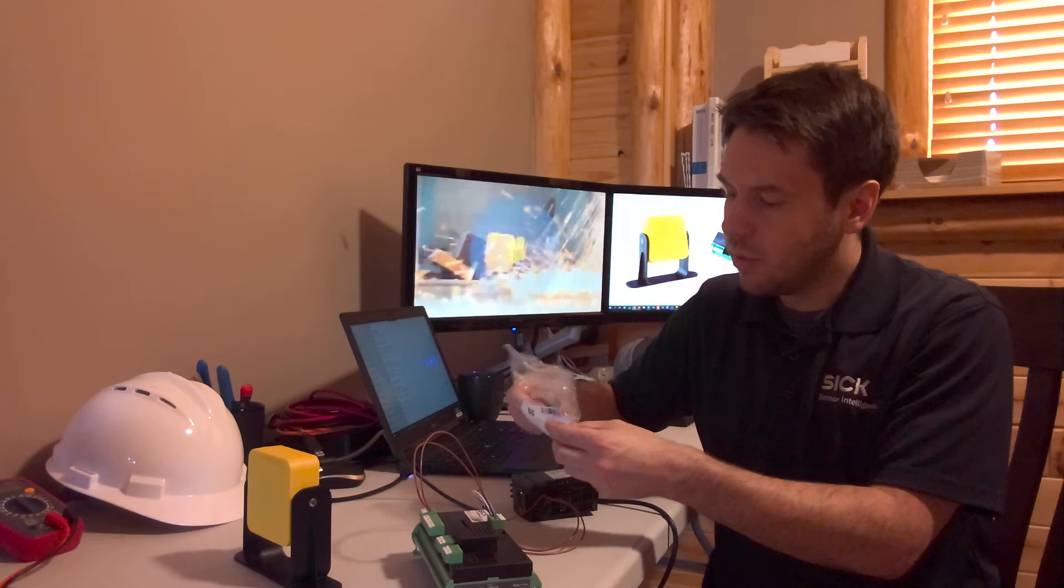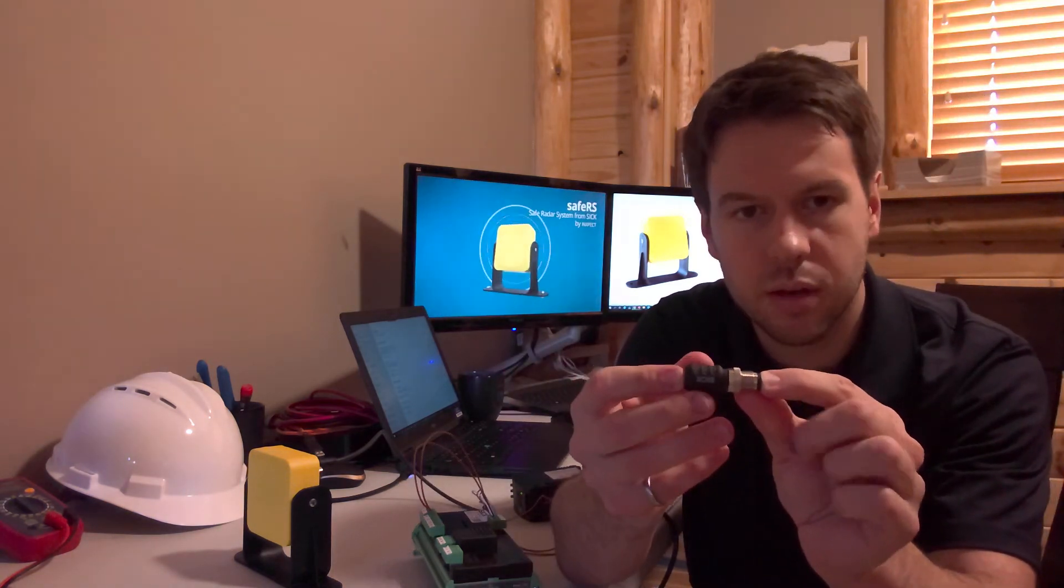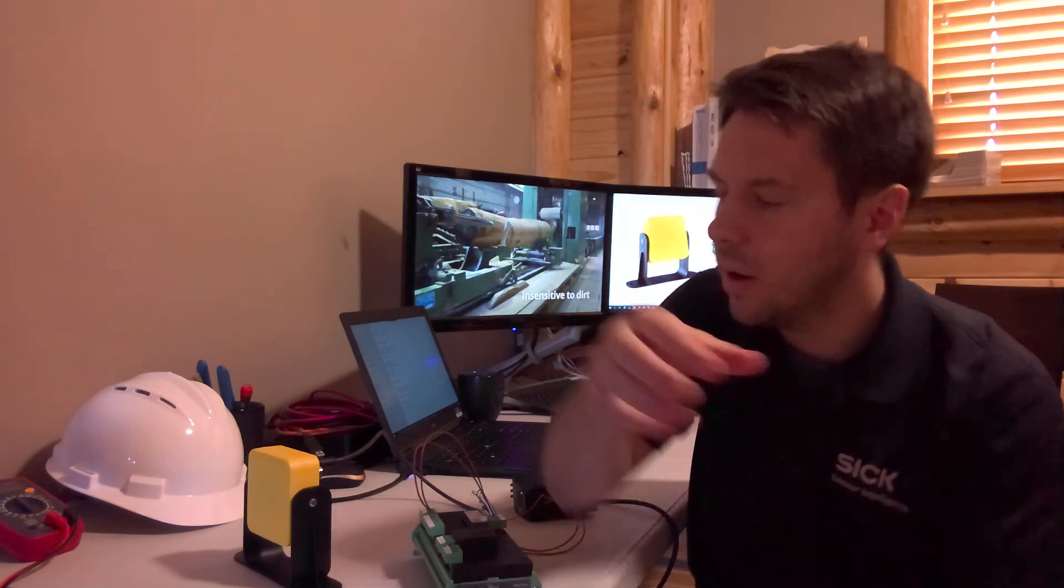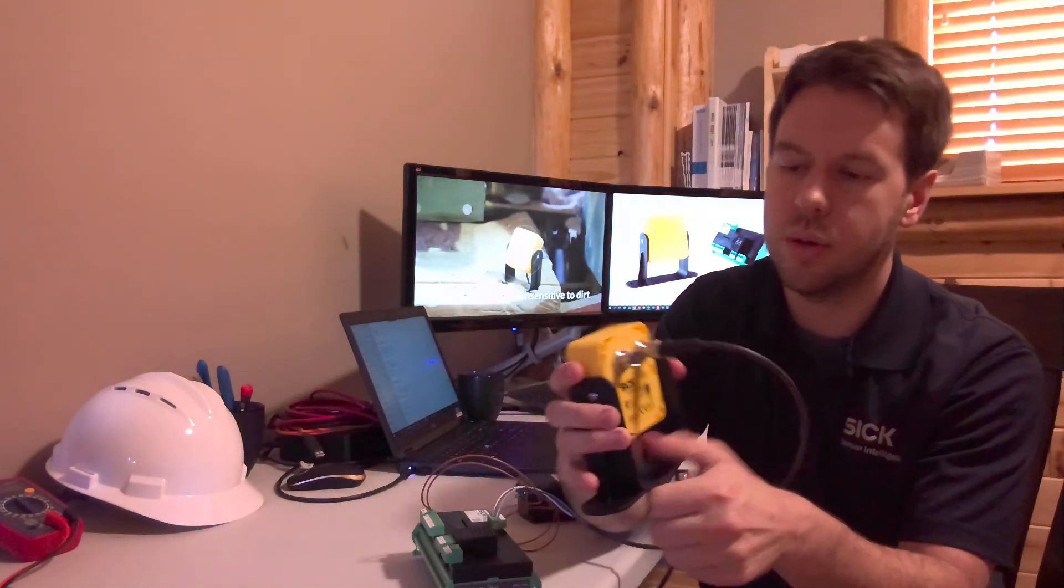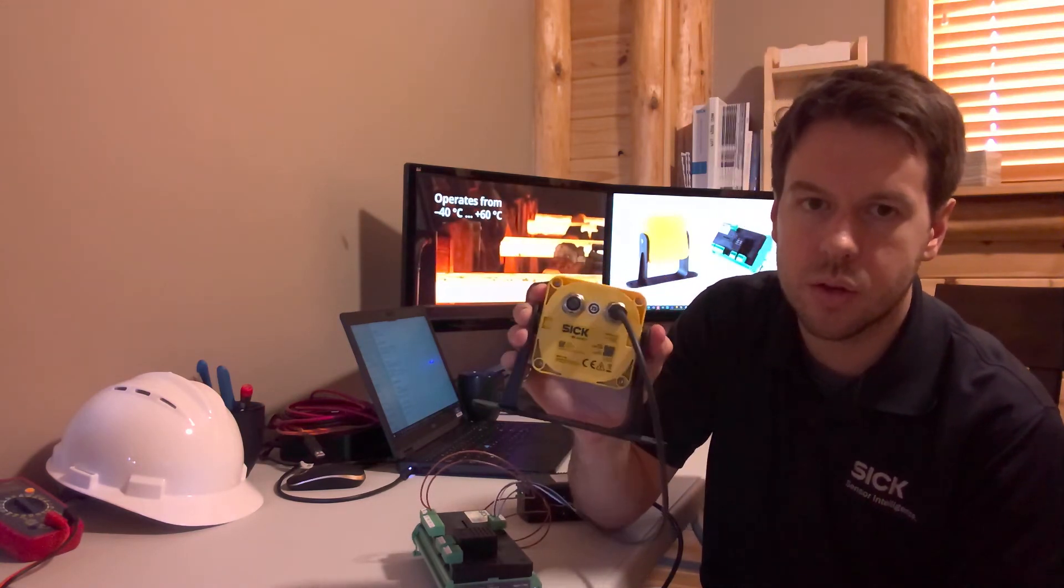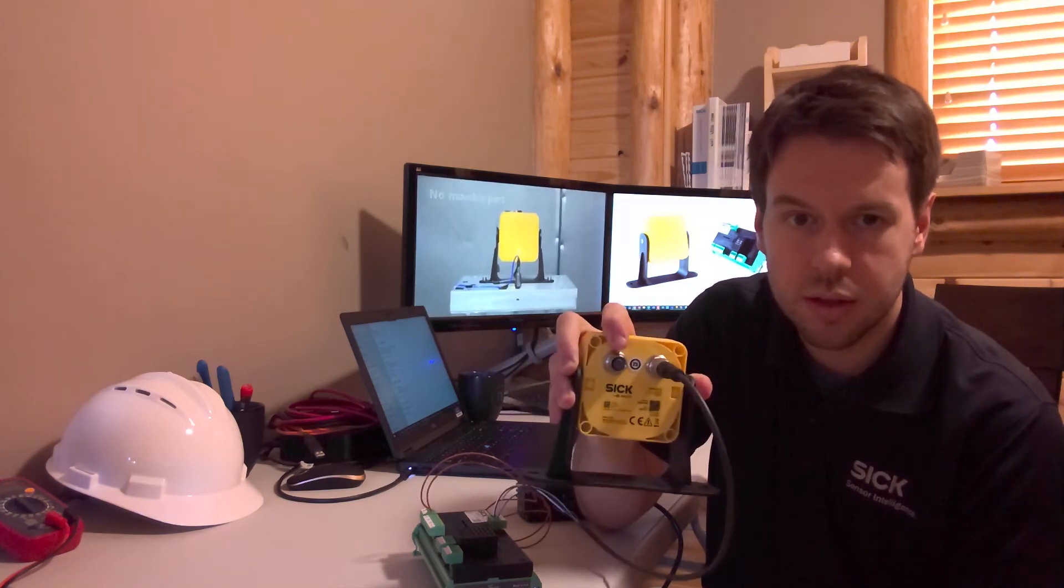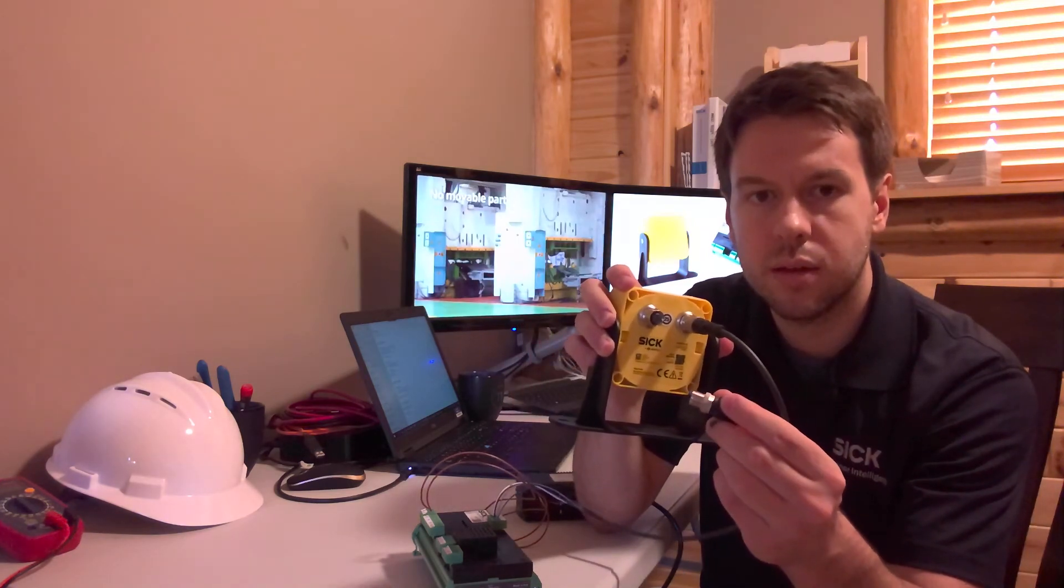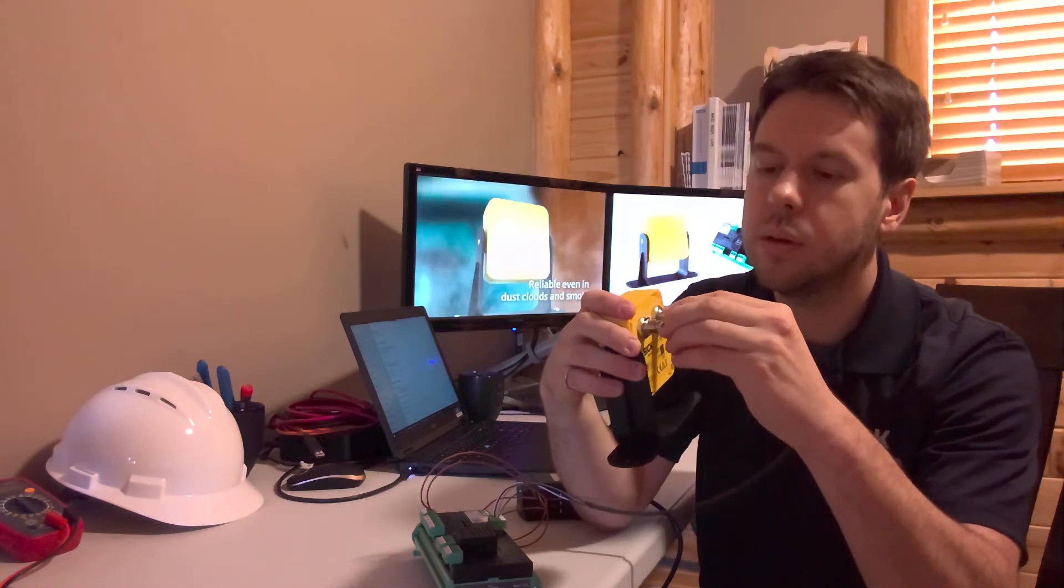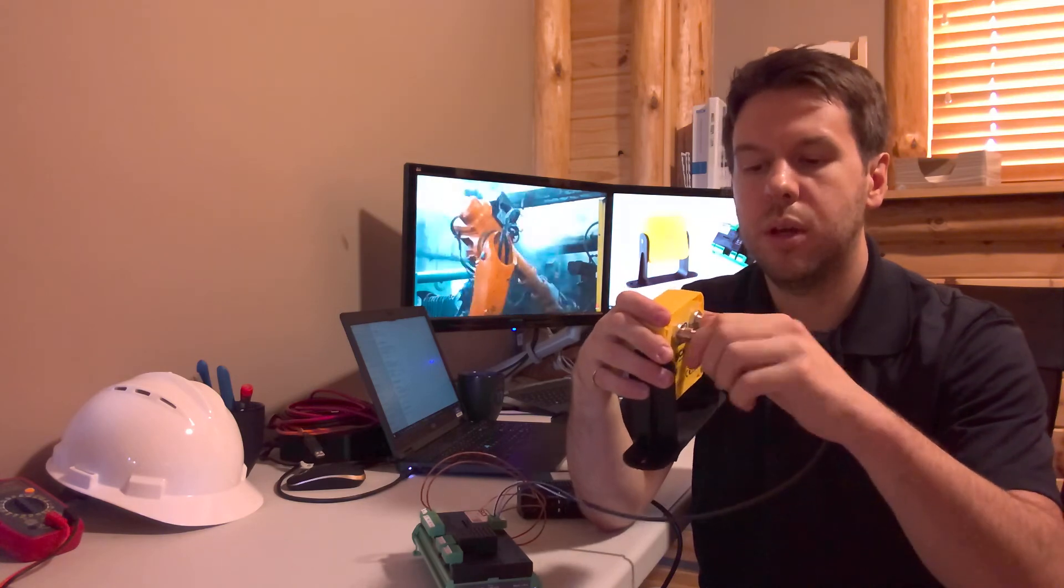The last thing we don't want to forget is the terminating resistor. Just your standard termination resistor. This is CAN bus safety, so we do want to terminate it. This will always go on the last sensor head or the last open connection. So if you have up to six of these, this connection would go on the sixth sensor head. Let's get that plugged in.